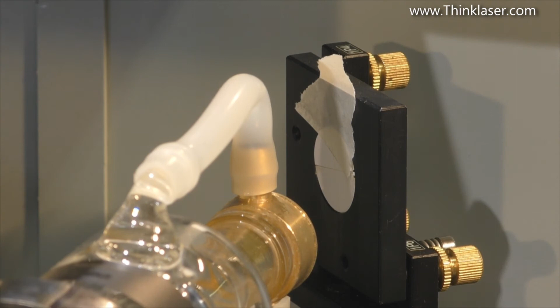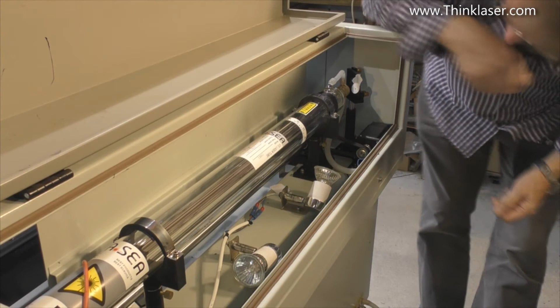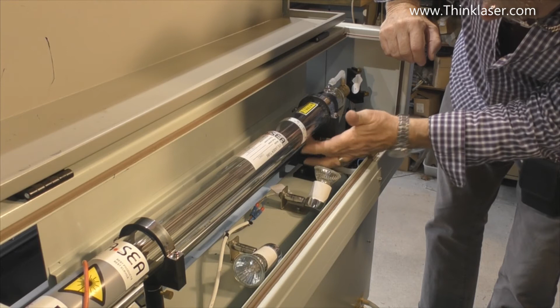So I would say it looks as though that beam has got to go up by about 2 millimeters. Now, how do I get the beam up by 2 millimeters? I want to lift both ends of the tube up by the same amount, i.e. 2 millimeters. We've got these screws on here, and underneath here we've got like a locking collar. Now, that locking collar can lift up and down. It's an adjusting collar. Twist it down so that it sits on the top of the pillar. So I happen to have a piece of perspex here which is 2 millimeters thick, and what I'm going to do now is that once this collar is sitting down on the top of this pillar, and I'll make sure that the one at this end is the same, I'm going to undo these two screws here, which will allow me to lift the beam up. And I'll put that spacer underneath there, and I will lock the screws back up.